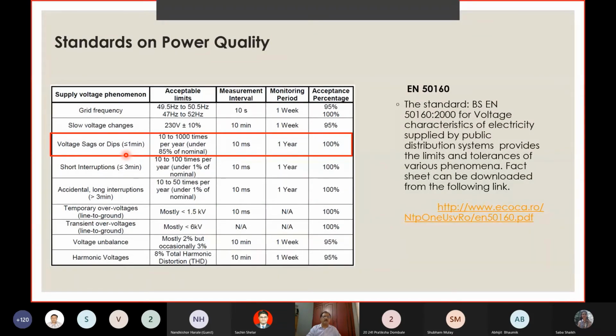Next to the harmonic and under power quality, next to the harmonic management, the next important management is the voltage sag or dips management, because this is actually causing a lot of losses in the industries. I do not know how many of you have witnessed some of your sensitive electronic loads like the VFD loads trip, while most of your ordinary electromechanical drive motors will be running still. Momentarily the power would have gone and come back, and if you are in the department, you would not have noticed that the power went out and came back. Human eyes would not have noticed this, but the tripping would have taken place, because most of the tripping takes place under 10 milliseconds.